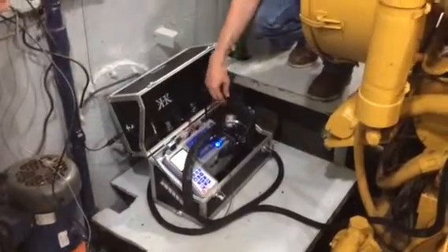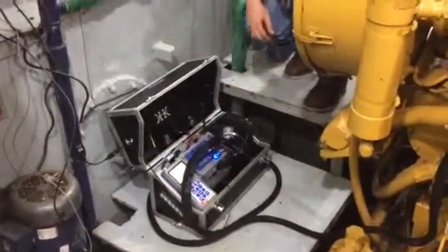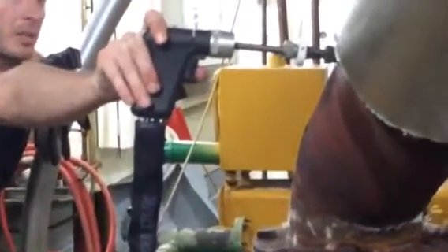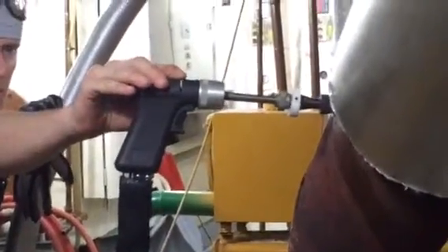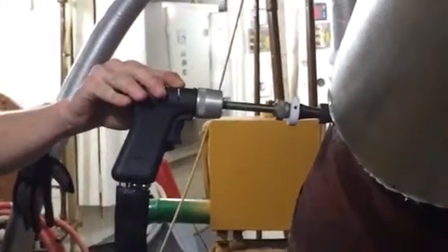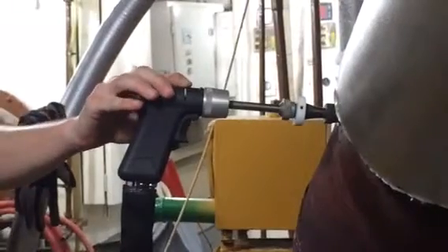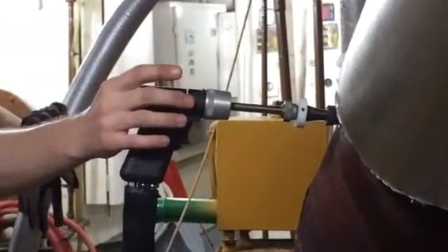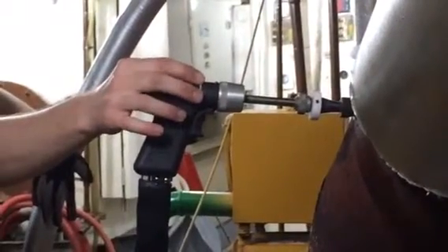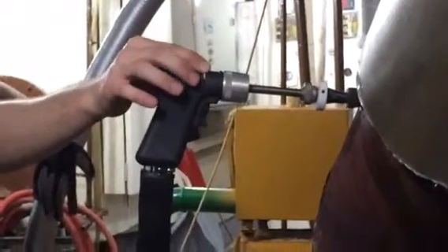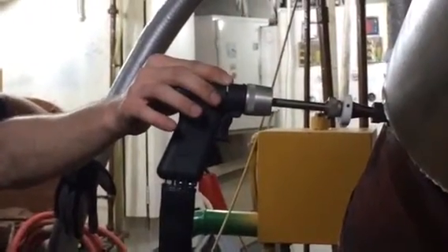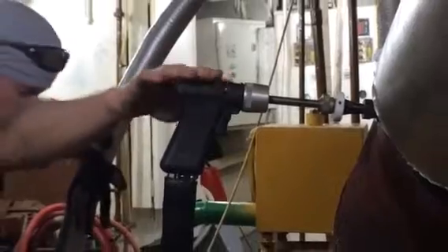The particulate matter is also taken from the sample probe, where a filter disc is installed, and 1.63 liters of exhaust gas is pulled through that filter disc, and the color, or the concentration of the particulate, is compared to a chart where a number is assigned.